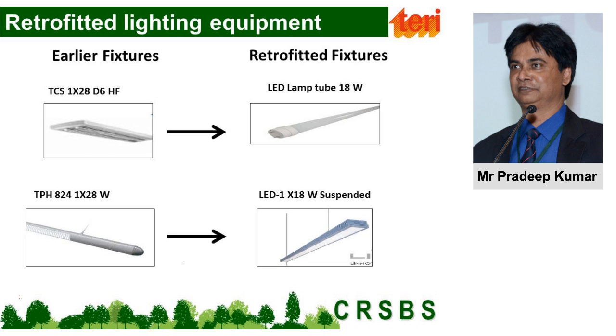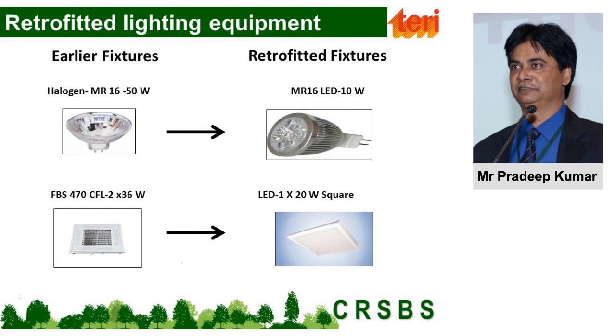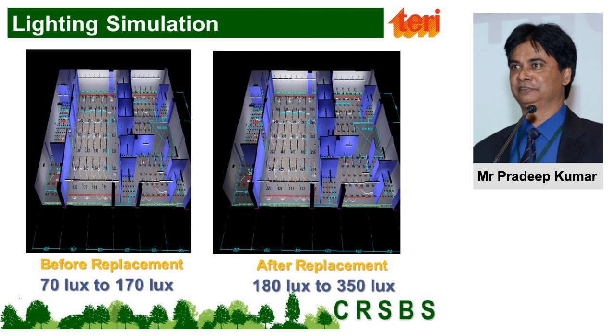And look at that, all the existing lighting sources, T5 and CFL, are very efficient. Similarly, halogens, 50 watt, can be replaced with 10 watt, and in the meeting rooms, 2 into 36 watt fluorescent can be replaced with a 20 watt square. So these were the different retrofit measures for the lighting. We have also done some lighting simulations. We used the photometric data. If I'm getting very technical, I will explain what this photometric data is. It is required for a luminaire whenever we do a lighting simulation, to find out how much light it is going to give at different work planes, or the vertical and horizontal sections.